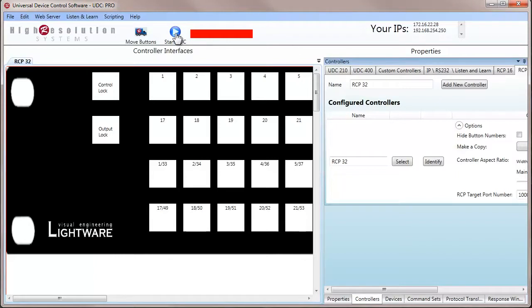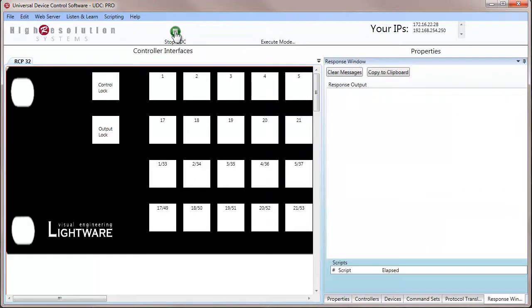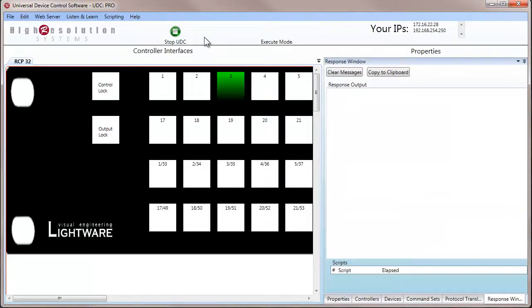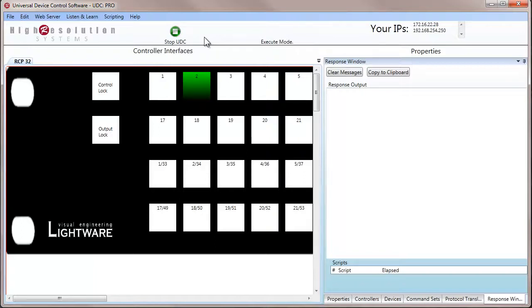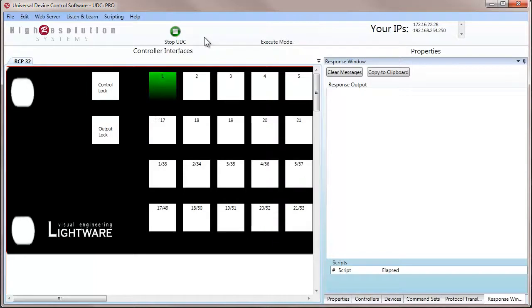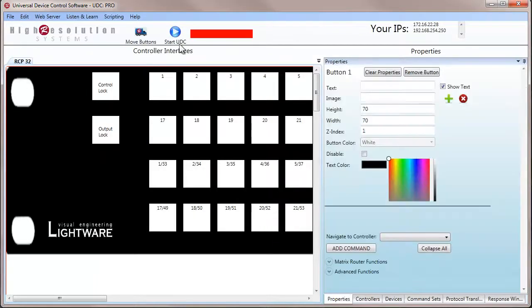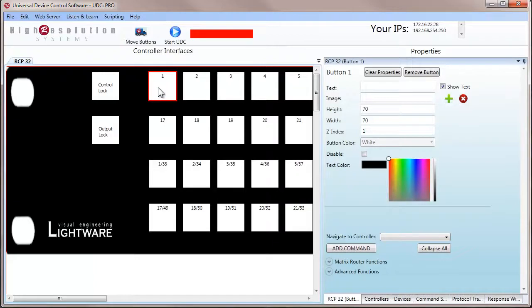So remember to enter play mode. When we enter play mode, this actually establishes the connection with the remote control panel and the UDC software. As you can see, I'm pressing buttons on the remote control panel, and it's showing in the software which buttons I'm pressing. That's verifying we have communication between the RCP and the UDC software.